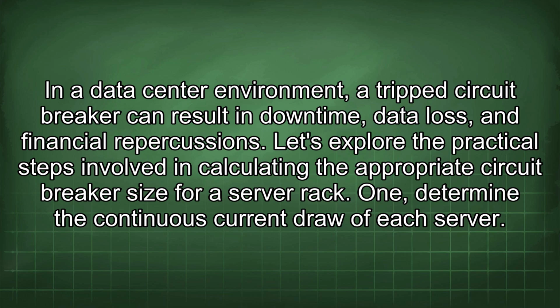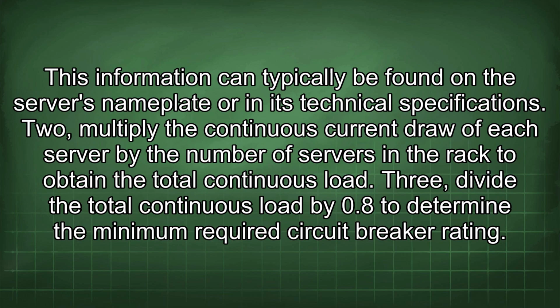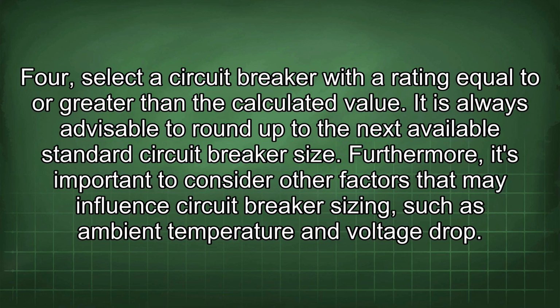Let's explore the practical steps involved in calculating the appropriate circuit breaker size for a server rack. 1. Determine the continuous current draw of each server. This information can typically be found on the server's nameplate or in its technical specifications. 2. Multiply the continuous current draw of each server by the number of servers in the rack to obtain the total continuous load. 3. Divide the total continuous load by 0.8 to determine the minimum required circuit breaker rating. 4. Select a circuit breaker with a rating equal to or greater than the calculated value. It is always advisable to round up to the next available standard circuit breaker size.